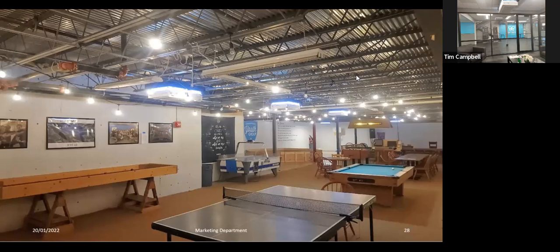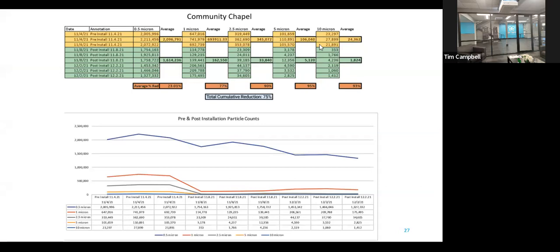But because this room was in the basement, it posed other challenges, meaning we saw very large particles, we saw very high spikes that we traditionally don't see because in a basement there's not a lot of airflow. You have a lot of things going on. Basements in general are dirty. They're susceptible to a lot of mold, fungus. So if you see this data here, you can see that the 5 and 10 micron counts are very, very high before installation. And then after installation, we reduce them drastically.